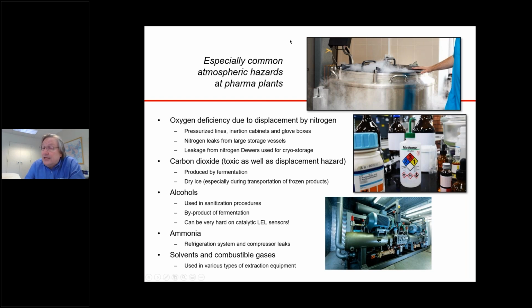When you swing the lid up, you'll see a boiling cloud of white vapor. That's not nitrogen that you're looking at. That's actually frozen moisture in the air that comes in contact with the very cold nitrogen. But it shows you what happens to the nitrogen. It's cold and it settles to the floor. So if you're in a closed and enclosed room, you are dependent on having really good ventilation that is continuously in place, turned on, and is sufficient to ventilate that enclosed room, or cryo bank, as we call these areas, with fresh air.